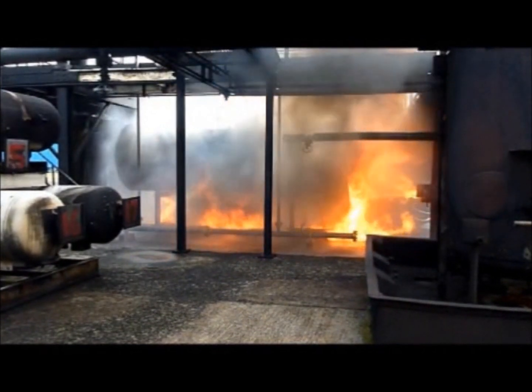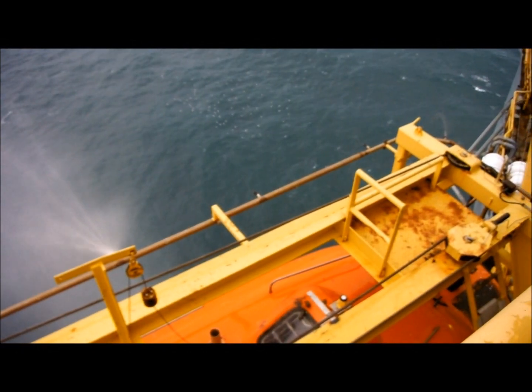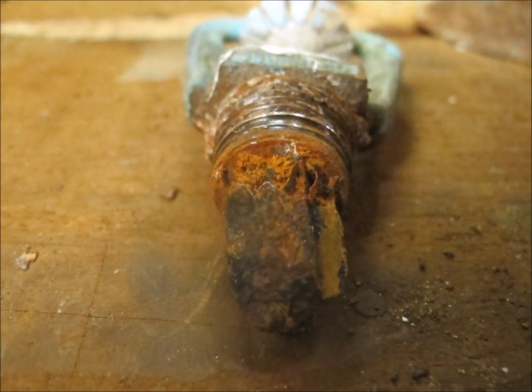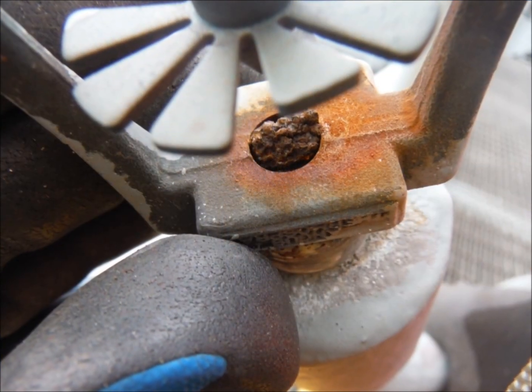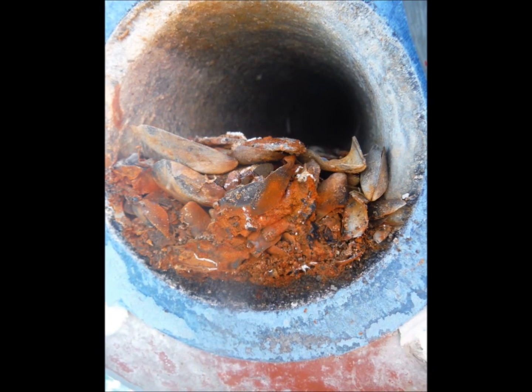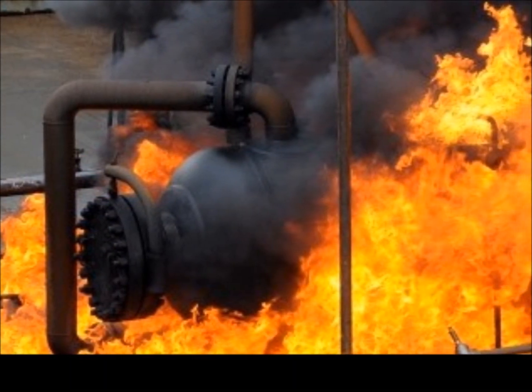There is a high risk of these systems failing through blocked sprinkler nozzles due to adverse effects that salt water introduces to the system. Nozzles block through delivery line scale, marine life, microbiological growth, concentric corrosion, salt crystallization, and failing filtration systems. All these salt water issues contribute to the risk of sprinkler system failing.